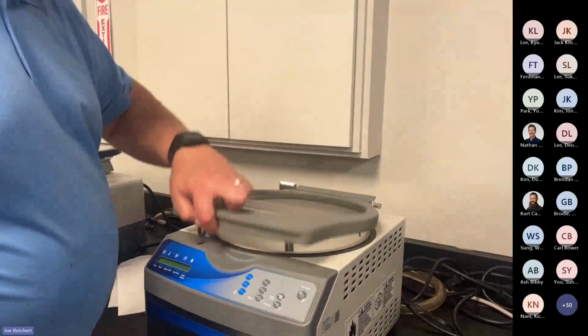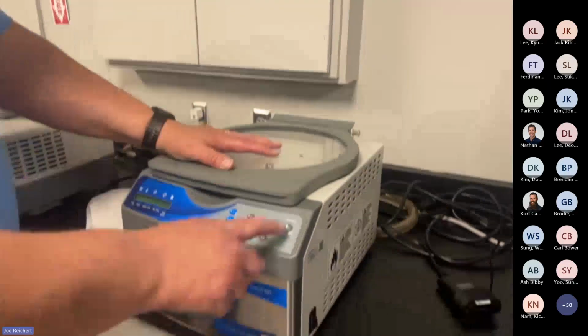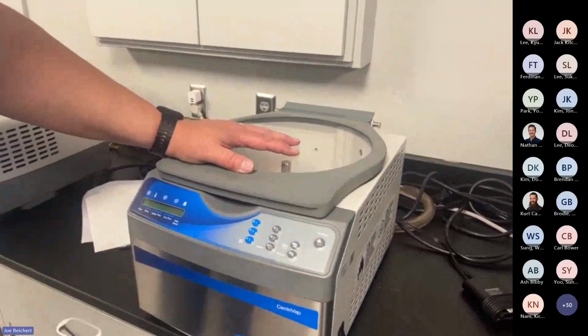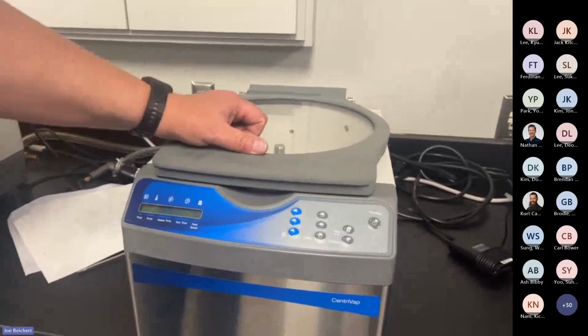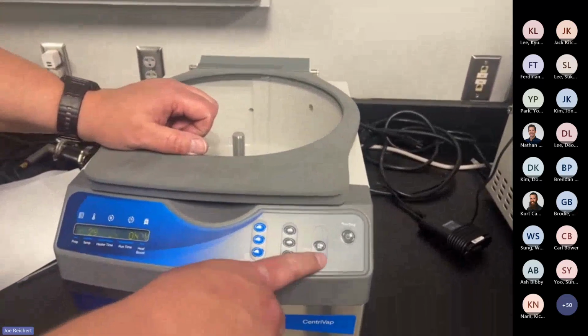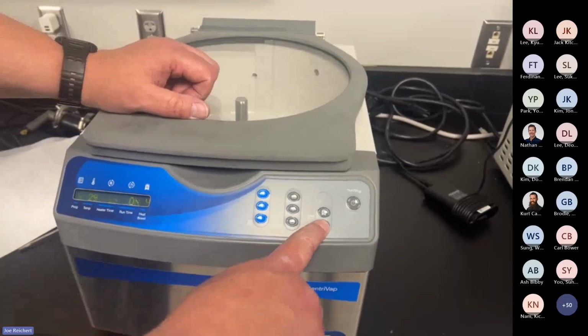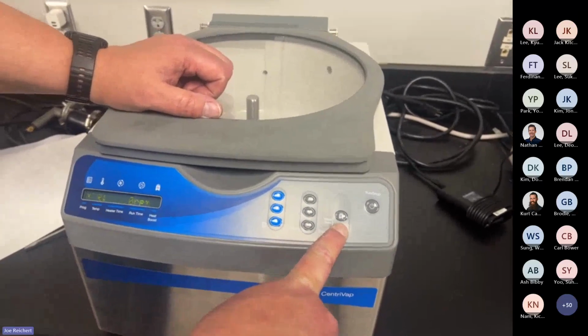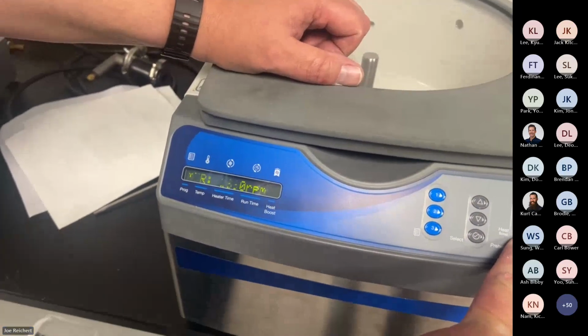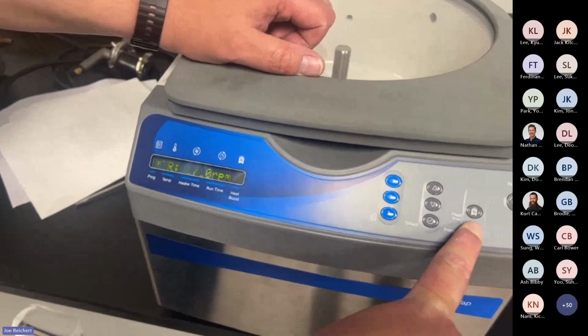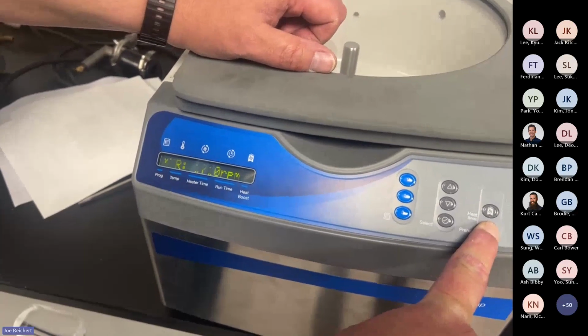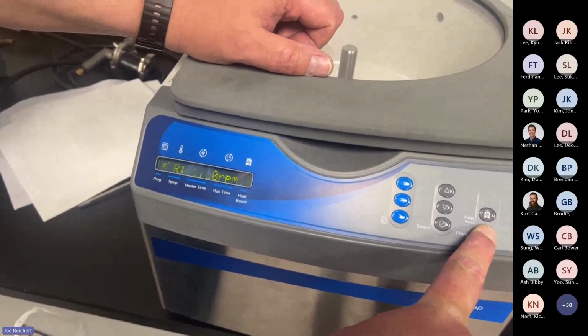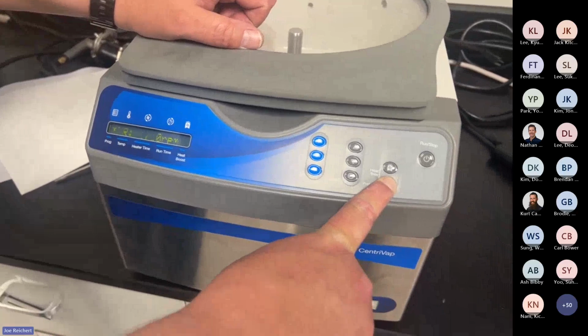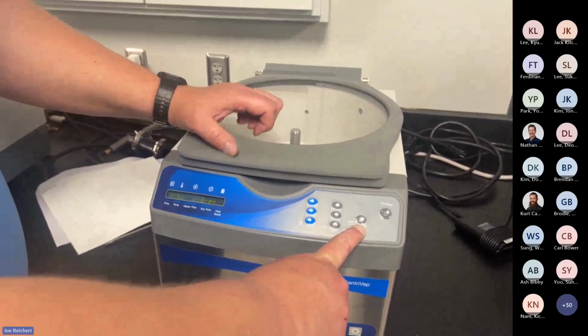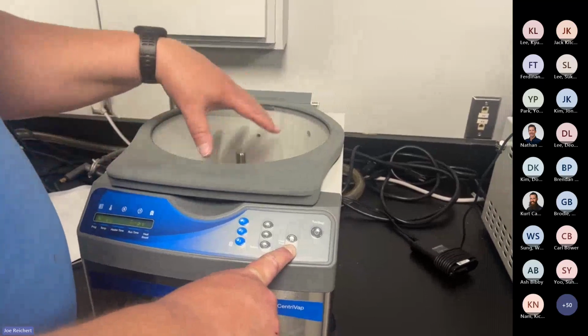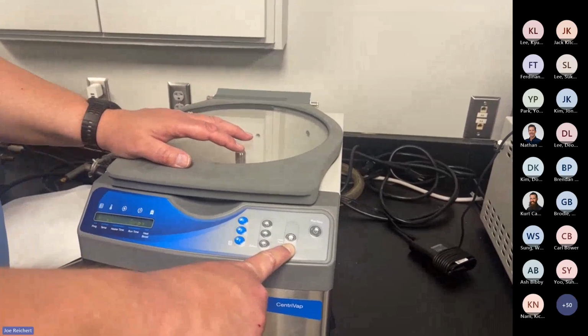Now, while the unit is spinning, if your customer's ever wondering how many RPMs there are when the unit is running, you can see how fast the RPMs are going just by pressing and holding the preheat button. Every unit has that. As you hold it, now your display changes to the RPMs. Looks a little weird on the screen through that, but it says 1710 right now, and gives you RPMs. Now on your 50 hertz units, I think the max is only 1400 or 1450, but here in the US on our 60 hertz power, we can go all the way up to 1800 RPMs. Once the heater is on and the bearings get warmed up, it'll spin a little bit faster.